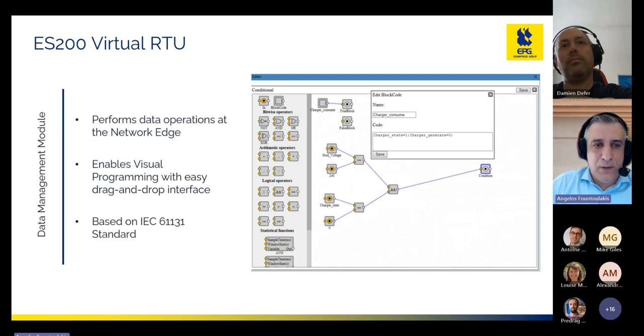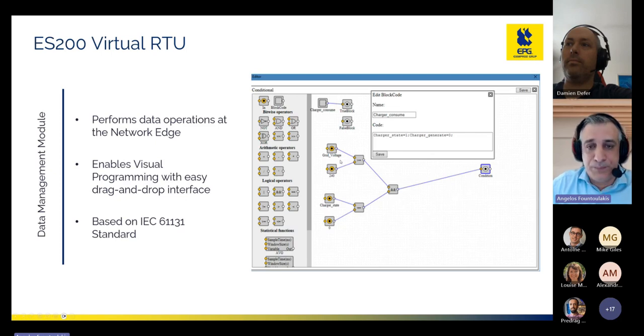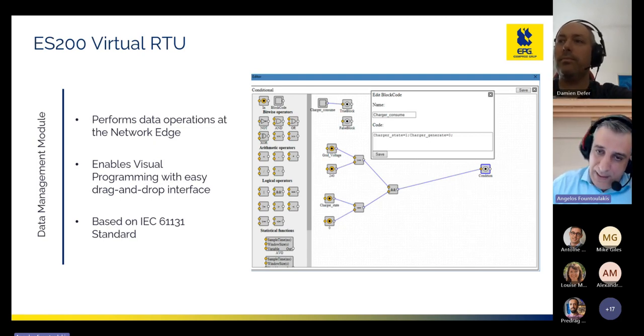Within the virtual RTU we have a PLC engine, a programmable logic engine configurable with a graphical interface. Based on the collected data points from the southbound devices, we can create rules with multiple operators that trigger events based on thresholds. For example, if the detected voltage exceeds 260 volts, that's an overvoltage condition, and as a result we execute an action to protect the network, such as reducing the power output of a photovoltaic site. I'll show a specific scenario later of how we use this PLC engine.